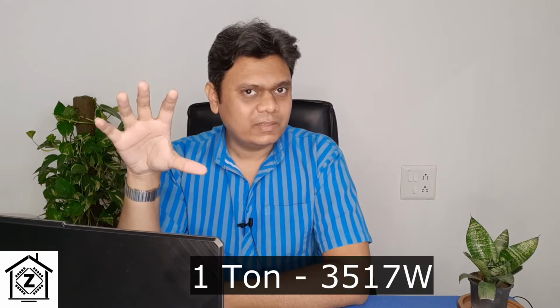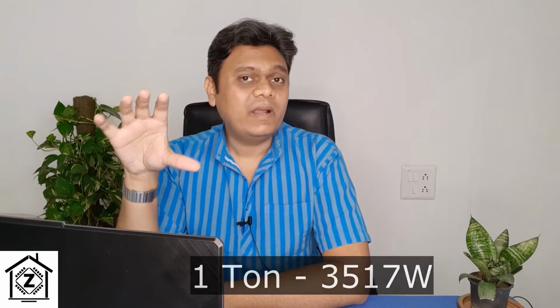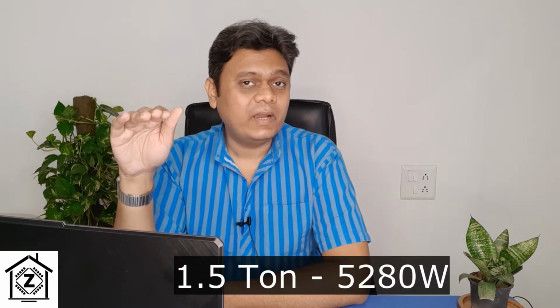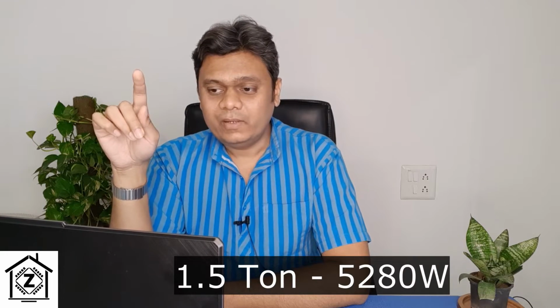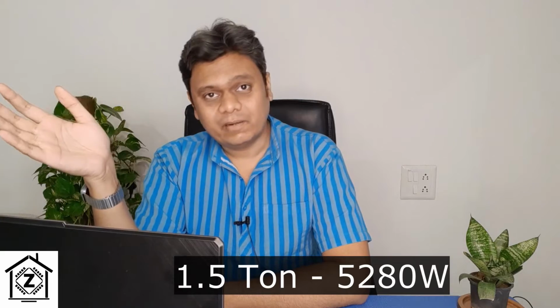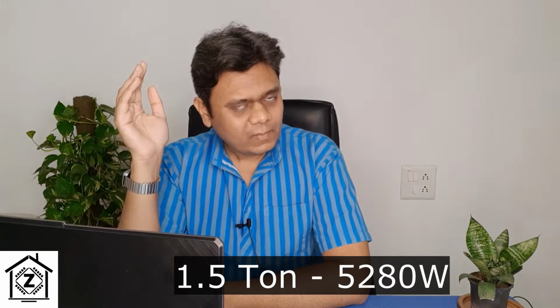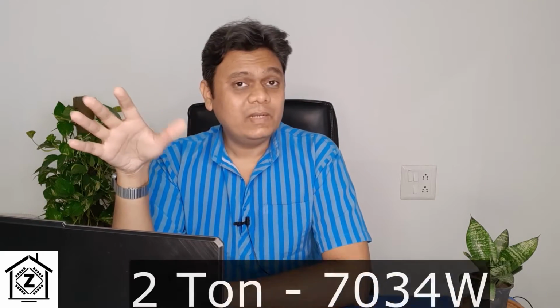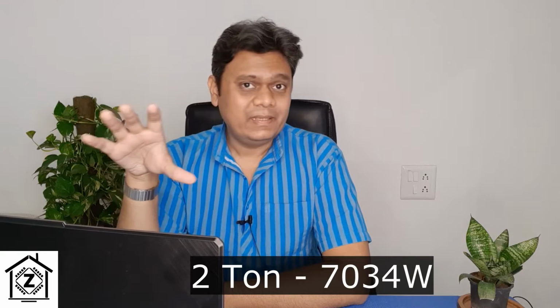A 1 ton AC generally has a cooling capacity of around 3500 watts. A 1.5 ton AC will have a cooling capacity of 5280 watts, that's the energy it can transport from indoor to outdoor. A 2 ton AC will have cooling capacity of 7000 watts. Yes, watts is the unit for both electricity and heat, although there's a small difference, the unit applies to both.